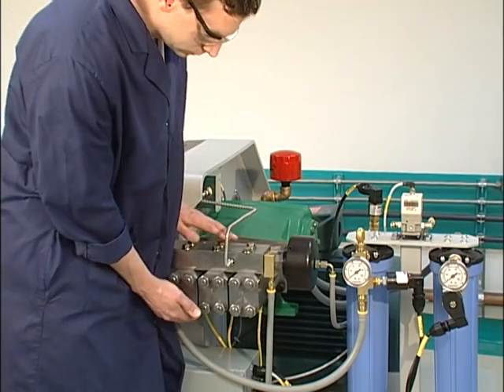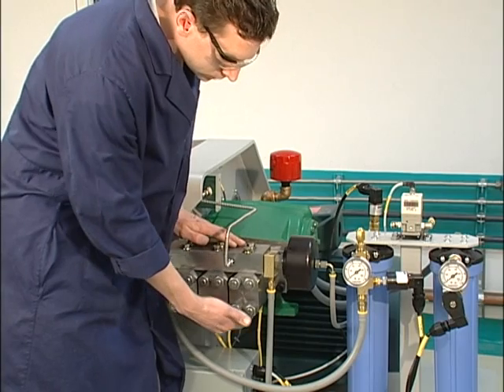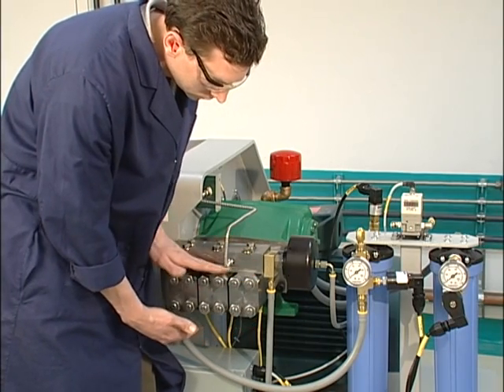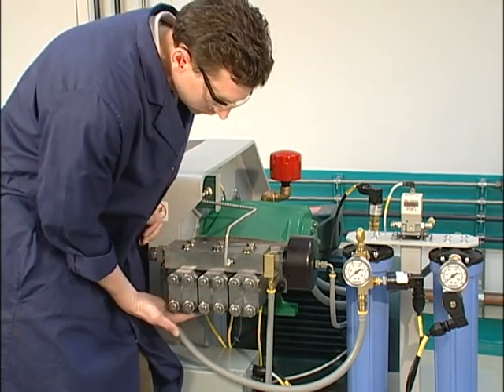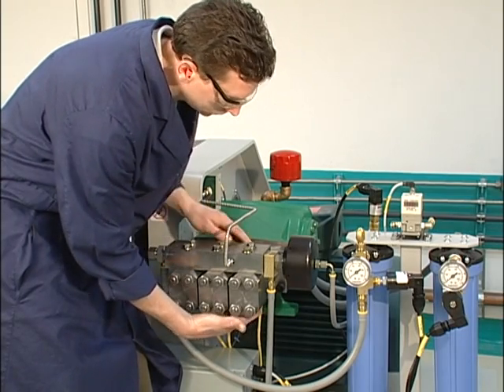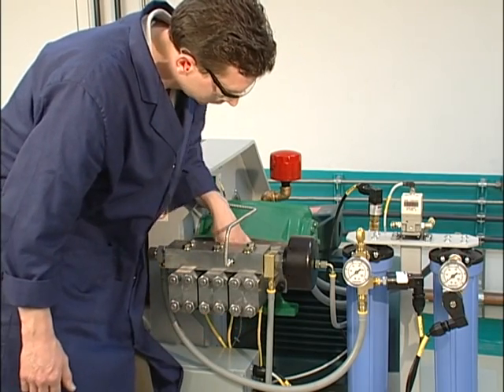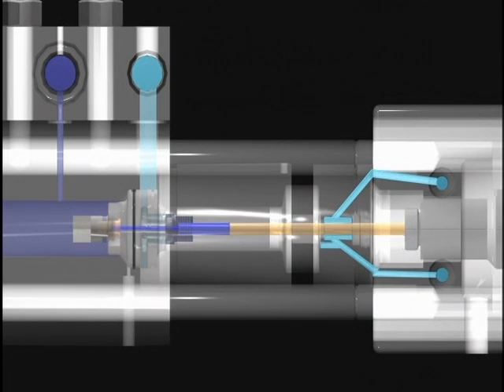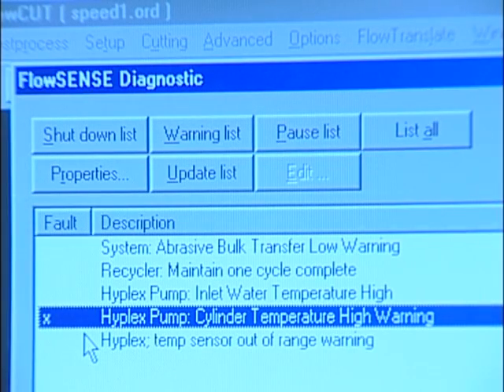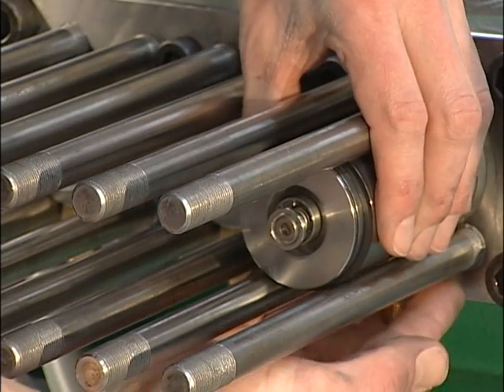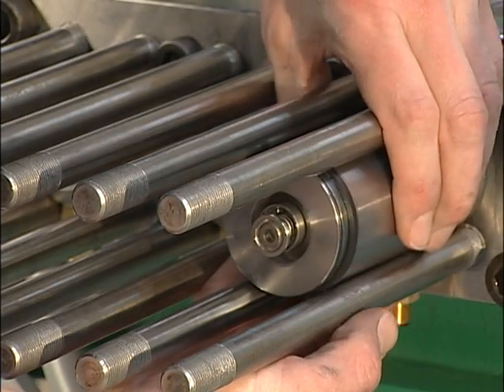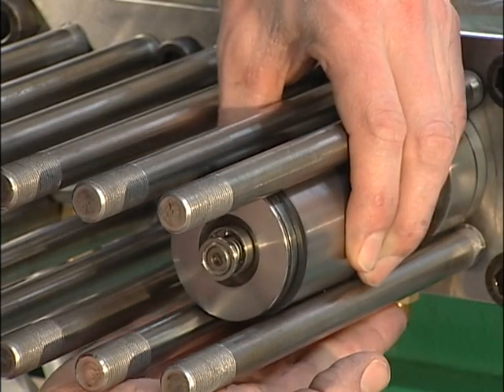An external leak or heat in the area of the seal carrier and dynamic seal may be indicators that the high-pressure pump requires maintenance. If a dynamic seal fails, it generally is an internal leak. The high-pressure water leaks past the dynamic seal and into the cooling water system. This can be detected by heat at the high-pressure cylinder or a low flow warning from the thermistor sensors. This procedure explains how to inspect and replace the high-pressure pump components.